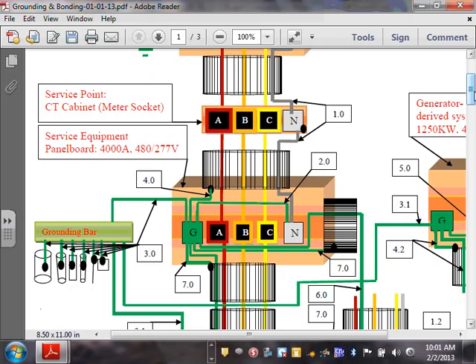Okay, so one way of doing it is to grab this ground bar right here, and you take this conductor, number 3, called the grounding electrode conductor. Grounding electrode conductor. When it comes to grounding, guys, terminology is very important. If you say grounding conductor, it's meaningless. You have to put a lot of adjectives. So it has to be grounding electrode conductor, or you can't find it in the code. If you say grounding conductor right now, you can't find it in the code.